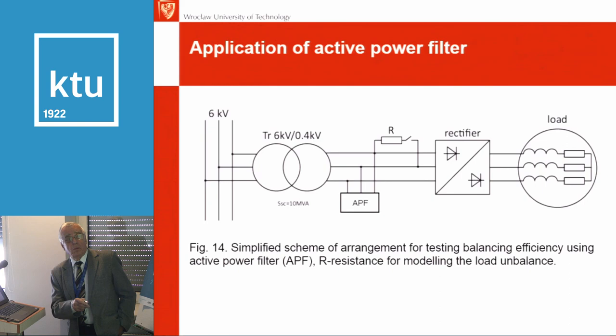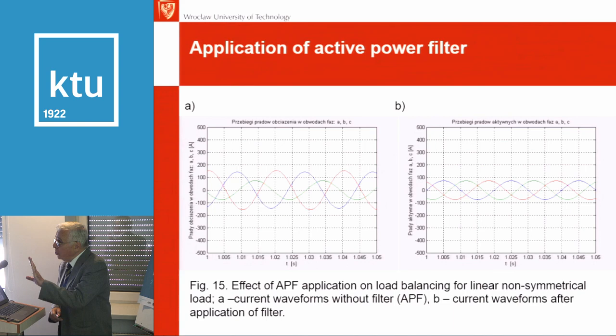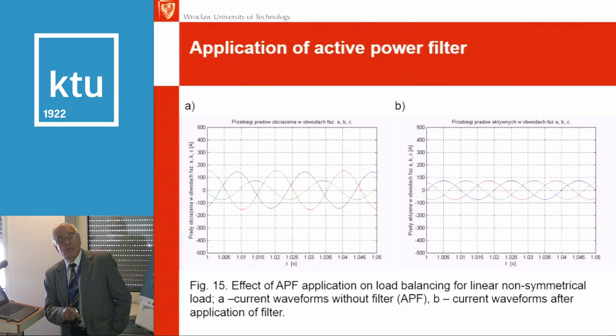And as a matter of fact, you see the effect of APF application, before application and after application. You see that's for asymmetry. However, with linear load, when the load is linear, there is no deformation. There is only a difference in the value. This value is also smaller. When we use these things, it is already symmetrical.